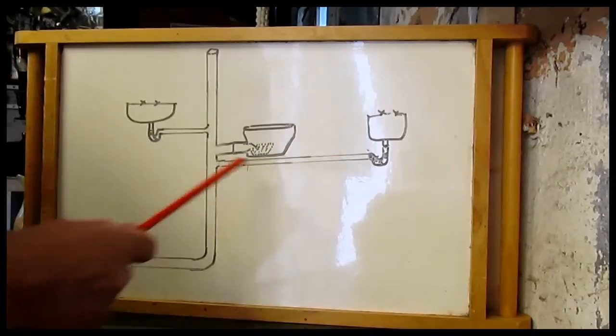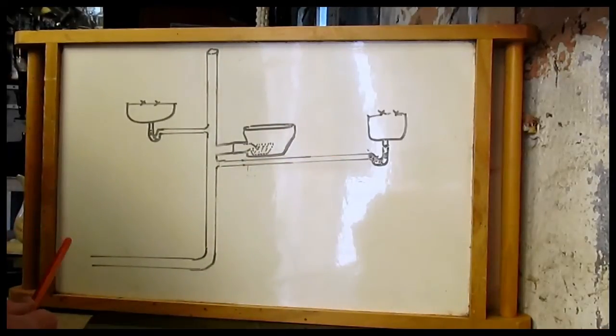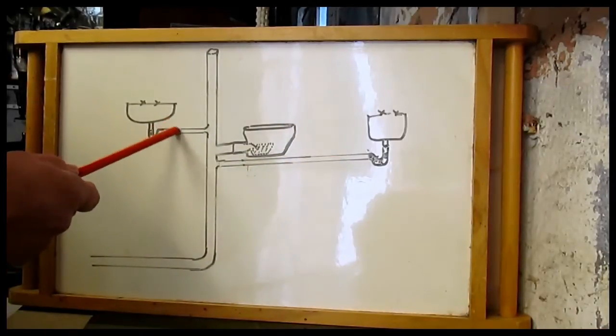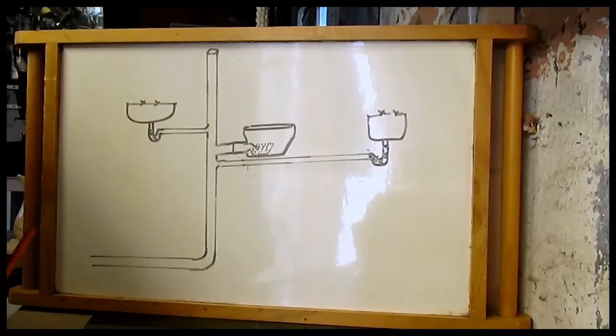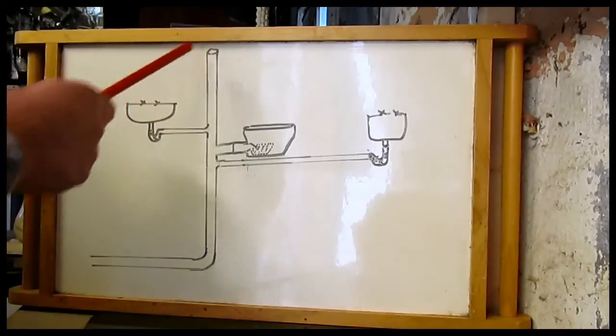A bath has always got to have an inch and a half pipe, which is 44mm, and a basin has always got to have 32mm pipe, which is an inch and a quarter. And the shorter the better. Right, so that's a typical installation with an open vent.